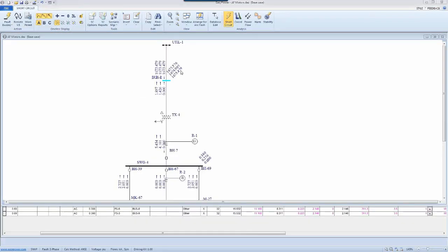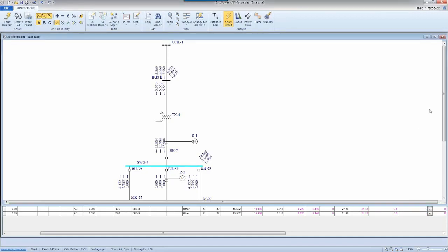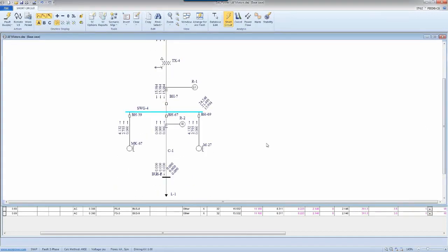It's very important to know that when we do the arc flash calculations, these values are not going to change. So again, for a utility, if I have a fault here, the values for half cycle, 5 cycle, and 30 cycle wouldn't change. But if I have a fault here, as an example, these are short circuit issues that we most probably know, and I just go over them as a review. For half a cycle, this is the contribution from the motor. At 5 cycle, the contribution goes lower. And at 30 cycle, the contribution goes even lower.